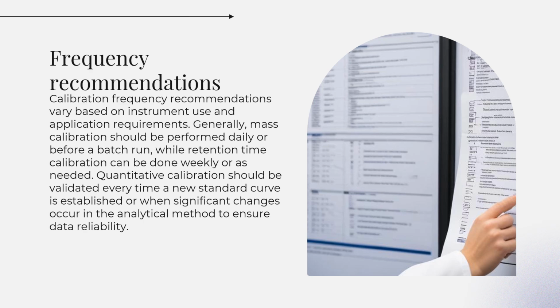Now what should be the calibration frequency of the instrument? Normally, the calibration of mass should be performed daily or before a batch run, while the retention time can be calibrated weekly or as and when it is needed. And mostly in labs, there is an intermediate calibration and a full length calibration. The intermediate calibration is carried out every 3 months, where crucial parts are calibrated, that is your linearity is calibrated, system precision is calibrated, that is your RT, and the response is calibrated. And in full length calibration, all the parts of the instrument need to be calibrated, that is, in 6 months it could be performed.